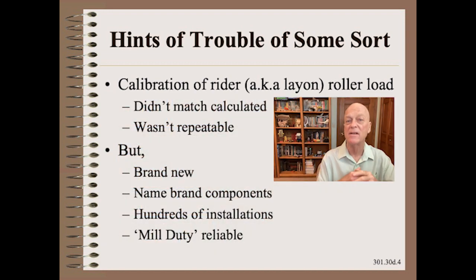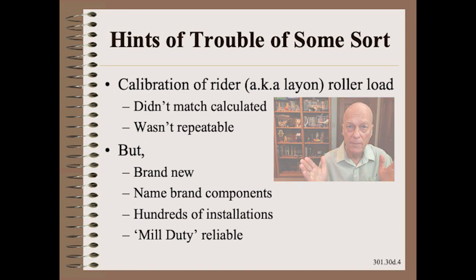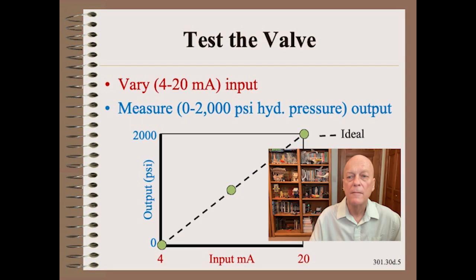What happened is not only didn't the calculated and measured lay-on rolls zero and gains match, they weren't repeatable. This was very odd because the builder had used hundreds of these name brand components, and they were always mill-duty reliable. If the system didn't calibrate repeatably, that meant that some component or the test itself wasn't right.